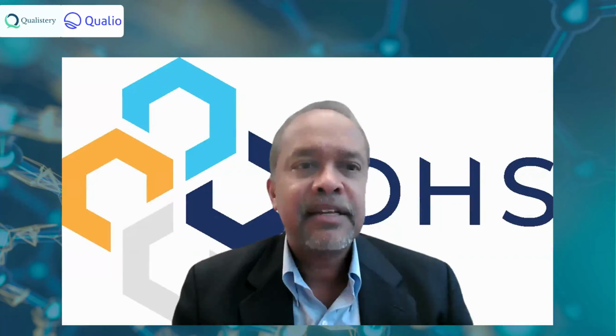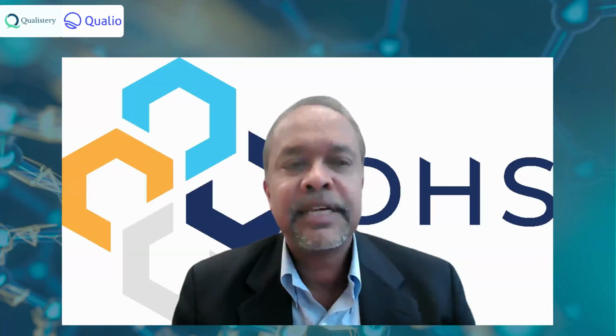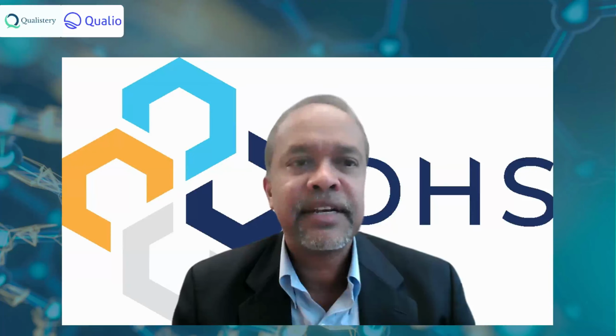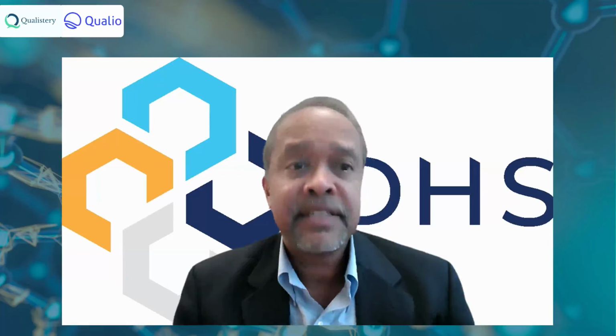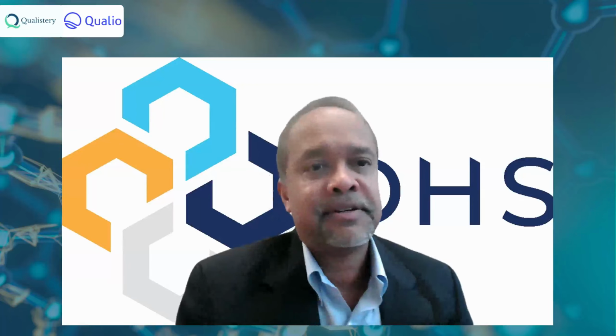Perfect. So Naveen, near the start, you spoke about the ISO 14971 lifecycle reviewed by the FDA. A general question: what's the recommended sequence for risk documentation under ISO 14971? Should a preliminary hazard analysis typically come first to identify the hazards and assess the initial risk levels, or can other approaches be used? We always do preliminary hazard analysis and even preliminary DFMEA because that becomes a guiding tool for engineering. I think it's also expected. So I'm going to say yes and yes, expected and good practice.